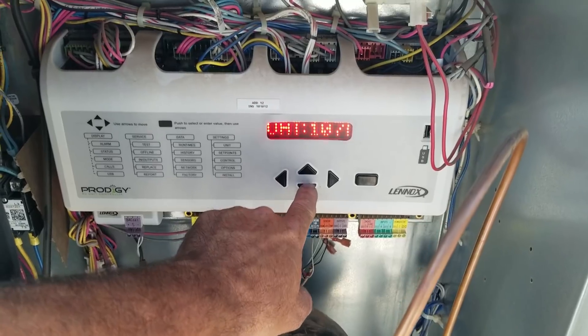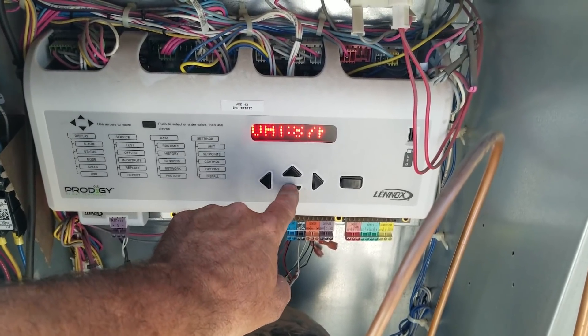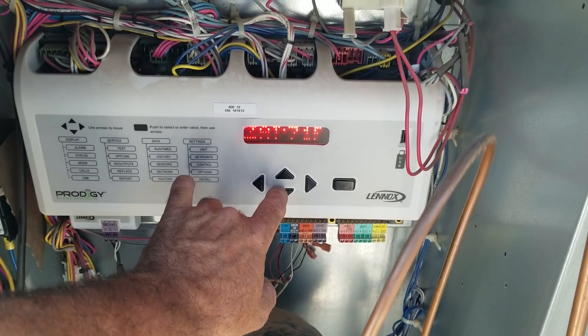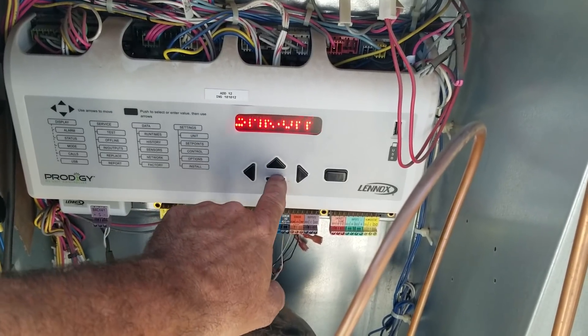It's still at minimum at 38%, it'll open up. Outside air is 87°, return air 71°. The IAQ in parts per million is going up — 1,300, but it's really only like 600. And if I go down to humidity, it's actually reading nice and low. That one doesn't throw you off when you look through here because you're like, well, maybe it's doing a good job at dehumidifying the room.